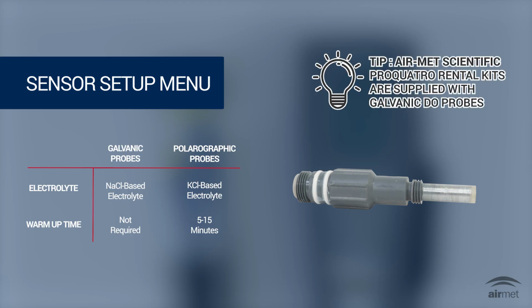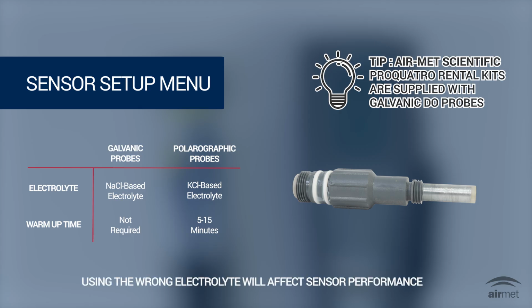The instrument default setting is Galvanic, and this is what we provide with our rental kits. Please change the sensor type to match the correct sensor. If you observe readings very close to zero or extremely high readings, for example 600%, your sensor setting type, Galvanic or Polarographic, may be set up incorrectly, and you should ensure it matches the sensor installed on your cable.